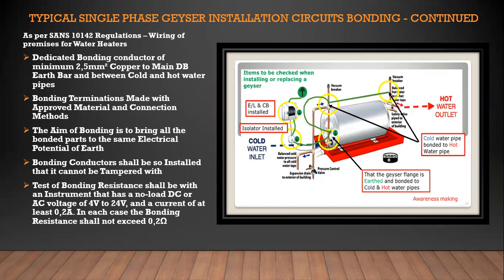Then we're looking at the bonding part of the geyser. That will come also in course 5. But yeah, there's a lot of repetitive things in those courses. From course 1 to 5, I repeat a lot of things because it's so important, especially the bonding conductors. What to use, what's the minimum size of wire, how to do the bonding conductors. I give you a practical demonstration in course 5. I've actually built a little model there to show you the correct way of bonding and terminating the bonding conductors onto the copper pipes, because that's where the high impedance or loose connections come in, and then the bonding actually means nothing. So how to use the bonding conductor, how to test it, and what's the maximum resistance of the bonding conductor in accordance with SANS 10142.